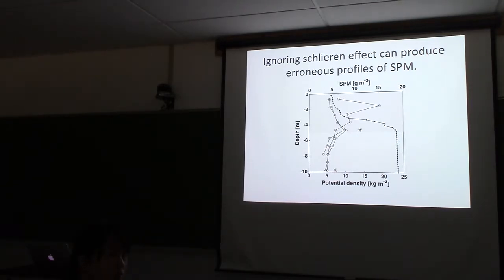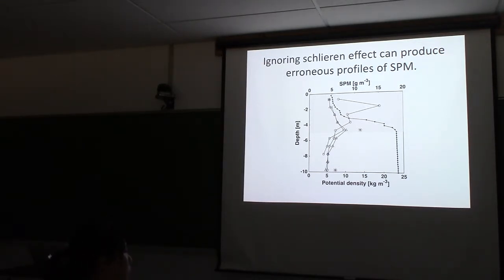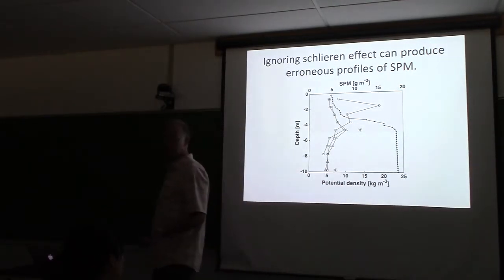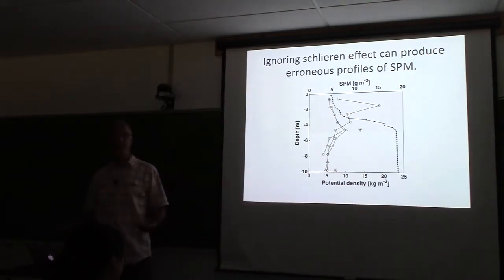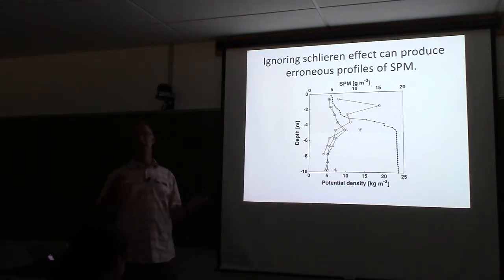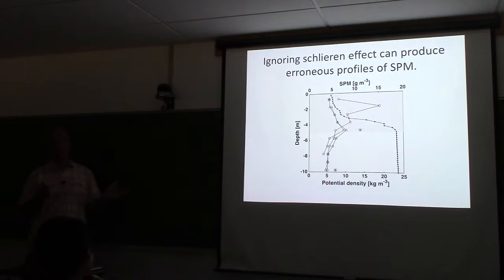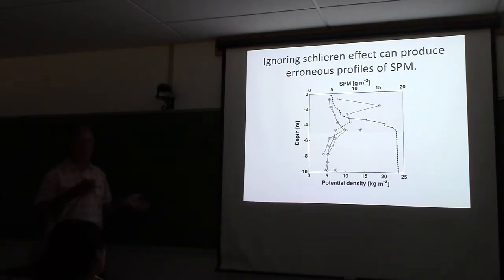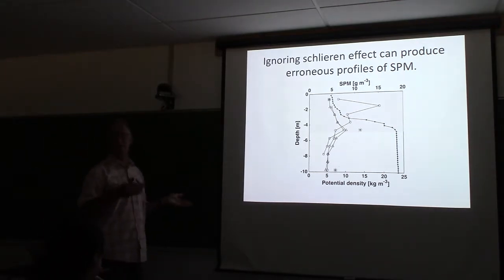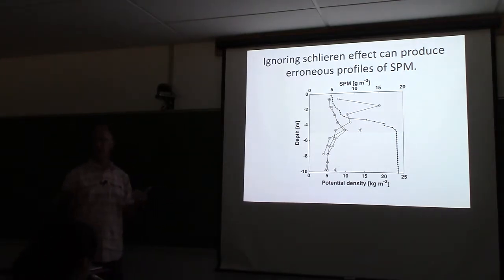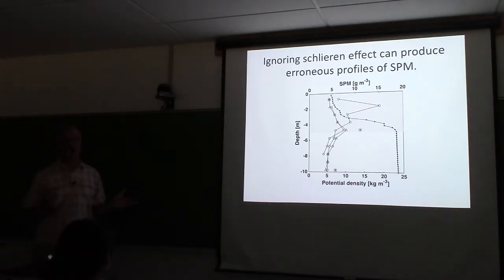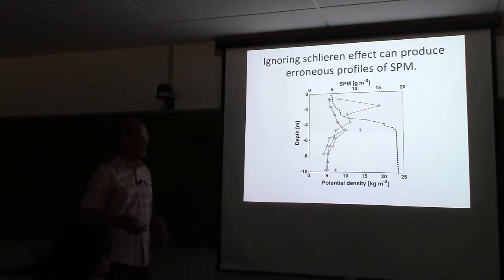The backscattering sensor provides a further independent confirmation. The concern was always how you can pump your sample when you know you might be destroying aggregates. But we've found that the relationship between the optical property and mass doesn't depend on size - so it doesn't really matter that you break them up, you still get a robust estimate.